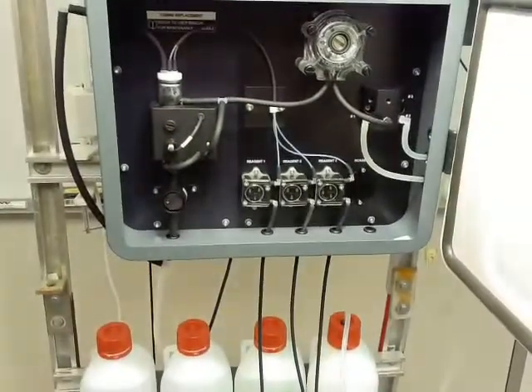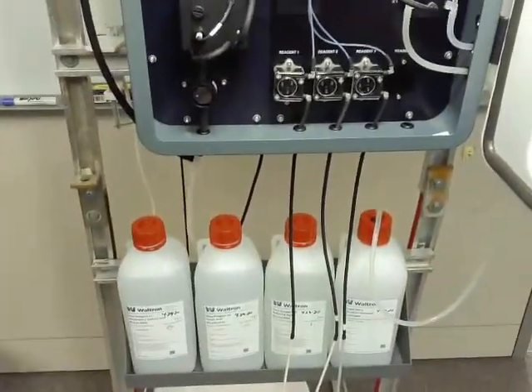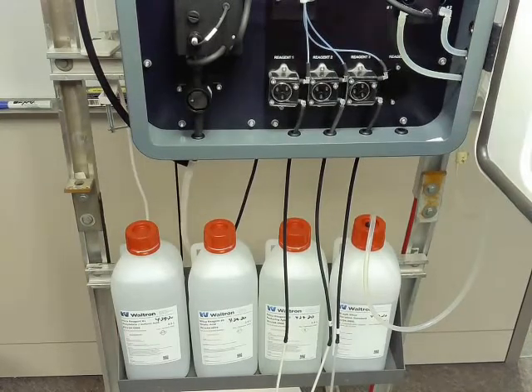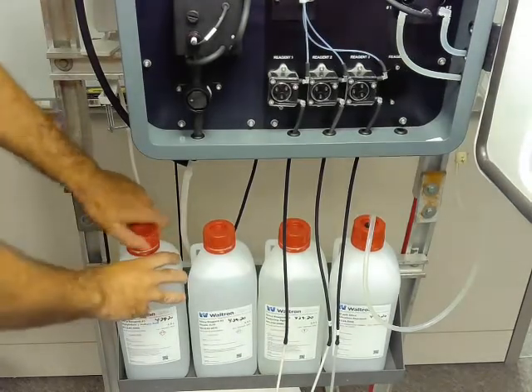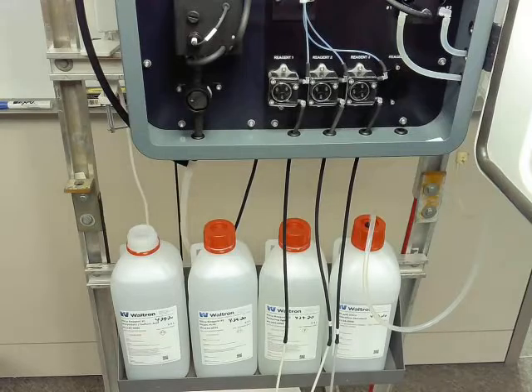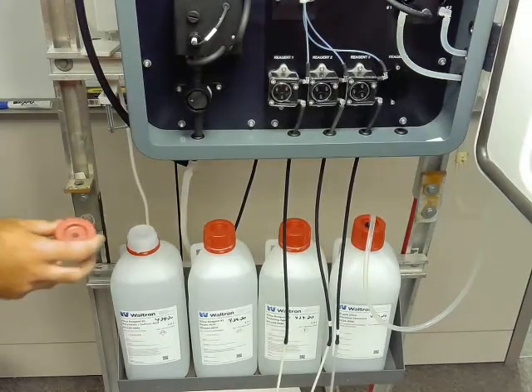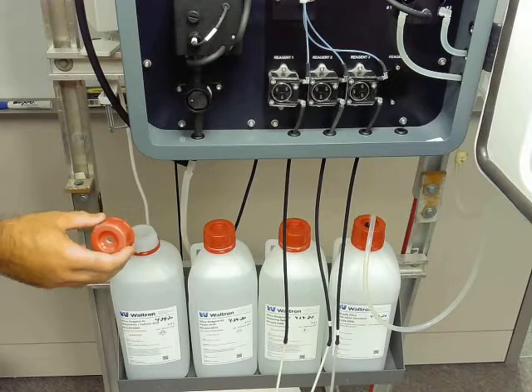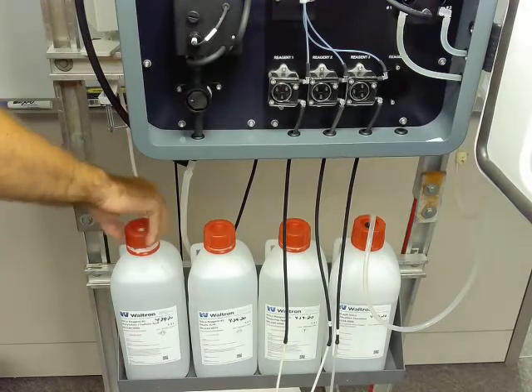As you can see on the bottom here, below the analyzer, we have our reagents. Again, with the hardness and the iron, there are a different number of reagents, and the bottles will also look different. The iron analyzer uses a smaller amount of reagent, so it's only a 1 liter bottle, and then the hardness bottles are 2 liter bottles, so they're a little round. But the idea is the same: when you get your bottle, you open it up, and with the analyzer comes a separate cap that has a hole and a grommet in it. Again, the caps will match the bottles that you have.